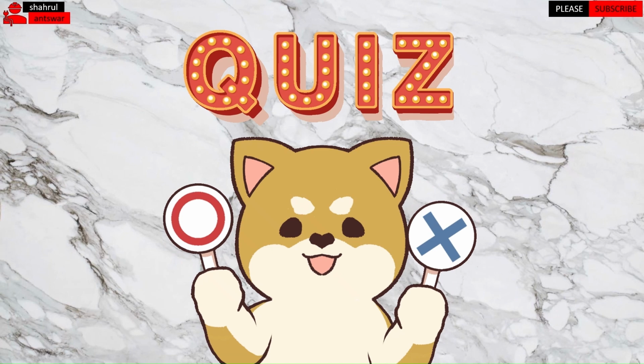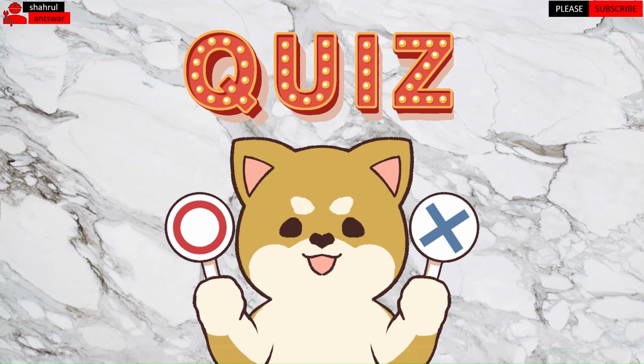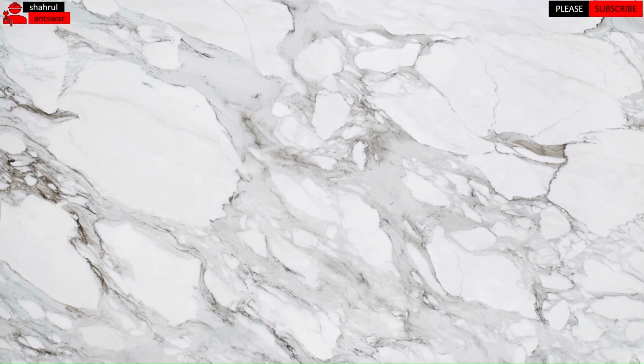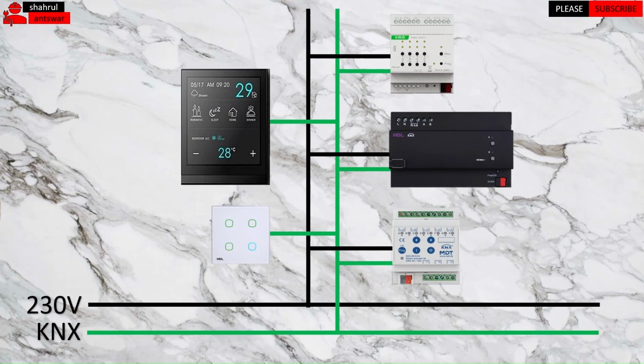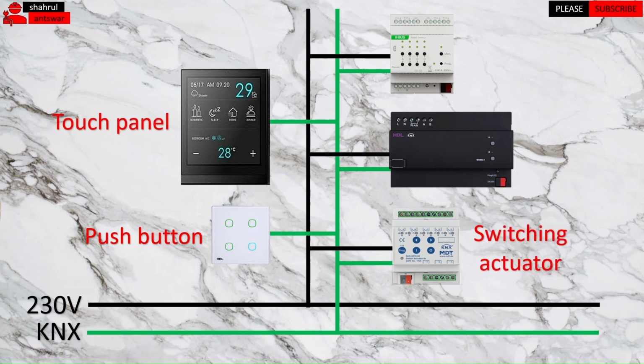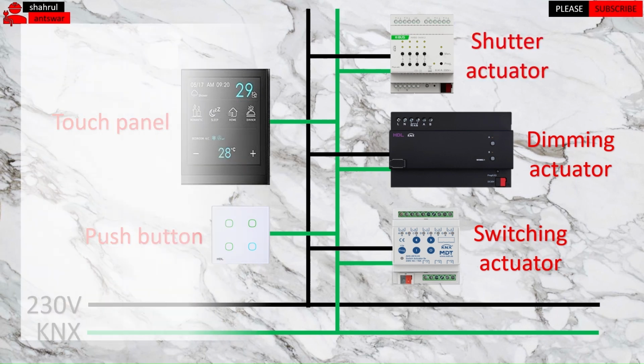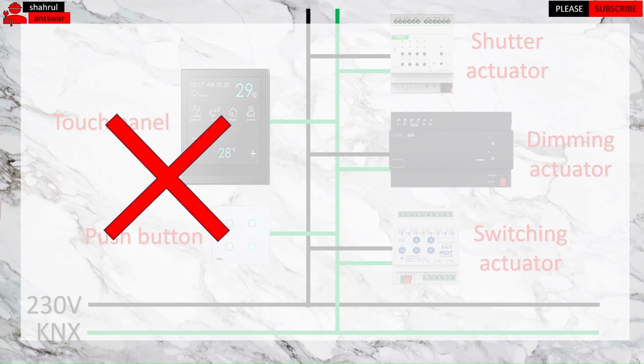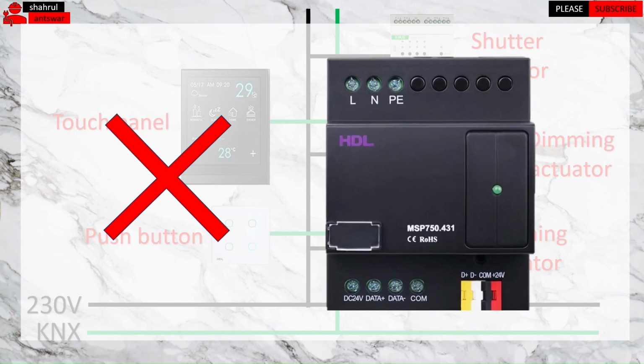Let's test the mind with the following situations to determine whether the minimal structure is met or not. KNX push button, KNX touch panel, KNX switching actuator, KNX dimming actuator, KNX shutter actuator. This does not meet the minimum structure of a KNX system. There is no power supply installed in the system. Without a power supply, other KNX devices will not be able to turn on.